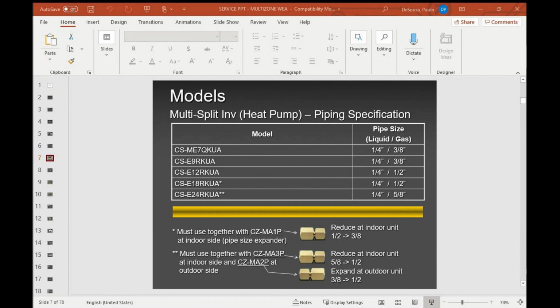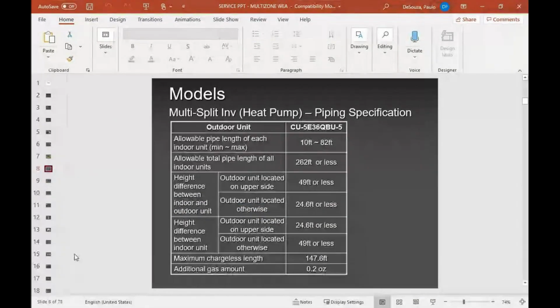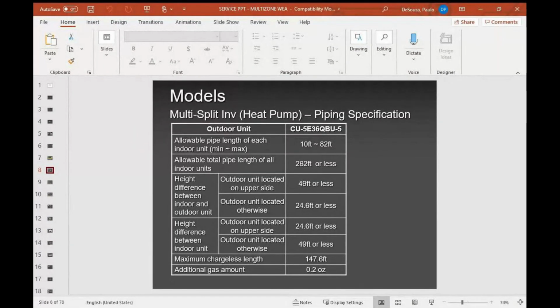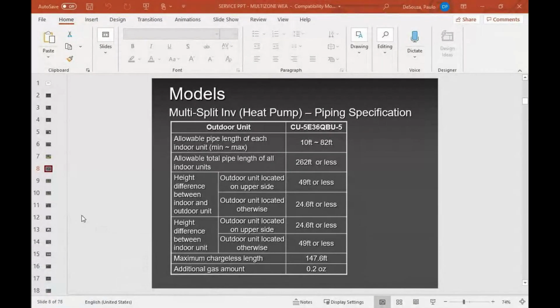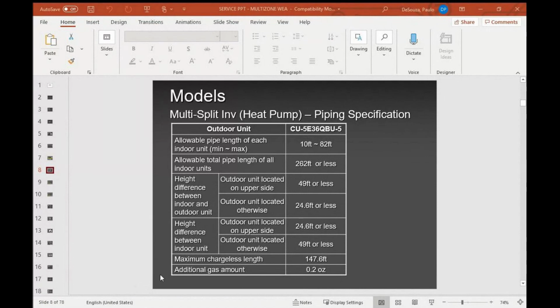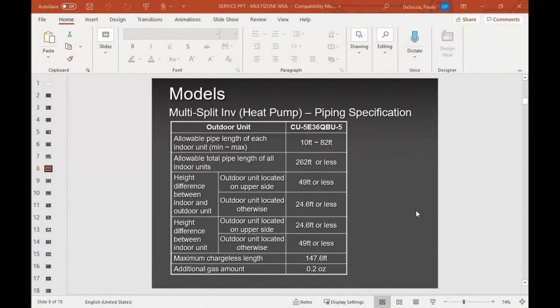Now we come to pipe length. Pipe length is also very, very crucial, because just in case you cross the charge-less limit, then you need to add refrigerant. People forget sometimes. So remember, total pipe length for our multi-zone, in this case 5-zone, is 262. For 4-zone is also 262. For 3-zone and 2-zone, it might be slightly less. So always remember to check the current installation manual you are working on. These slides are just for you to get an explanation, the hang of it, of how to go about things, how to do things in the right way. Okay? So always remember to obey the height difference, the length.